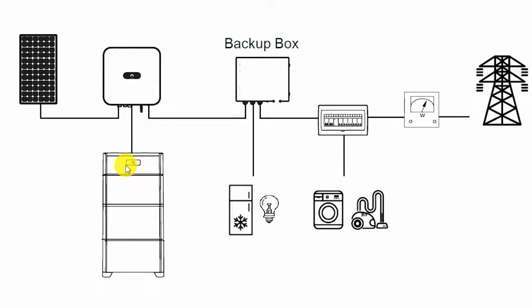Apart from the energy meter, we will also need the PV inverter, the battery, and this contactor box, which will put us into island mode in case of a power outage and feed a special output to critical loads, allowing us to use electrical appliances or any load we consider appropriate during a power outage.